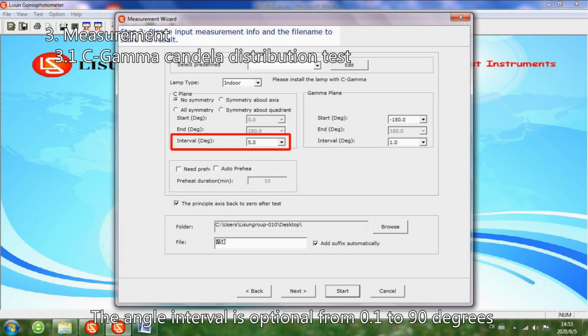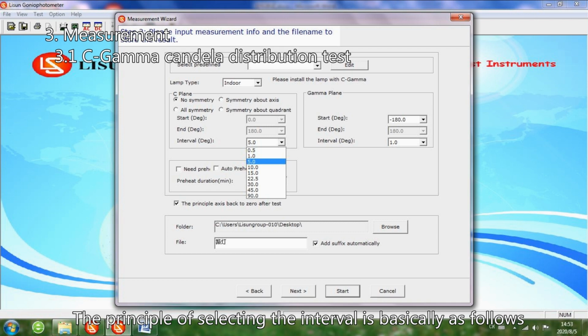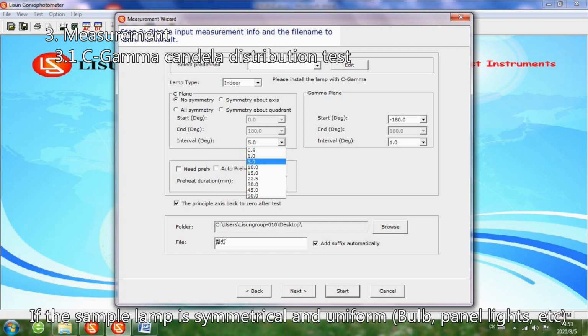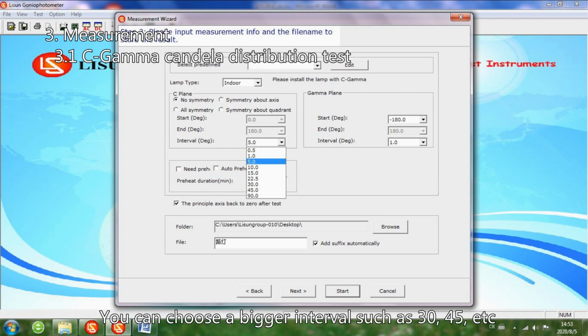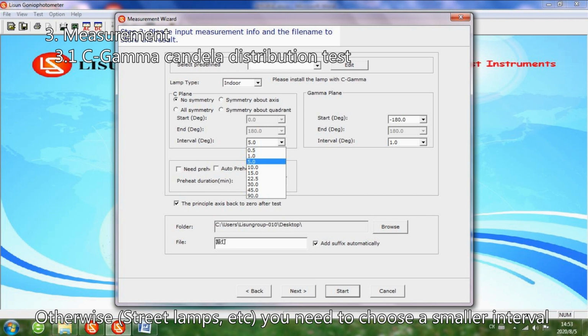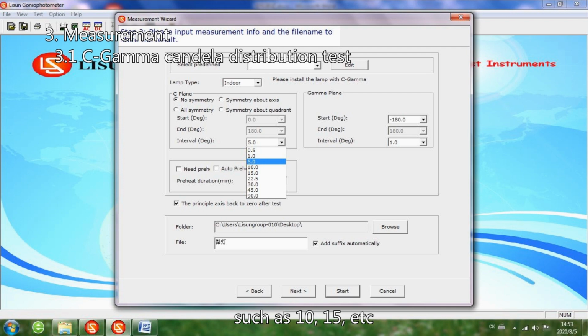The angle interval is optional from 0.1 to 90 degrees. The principle of selecting the interval is basically as follows. If the sample lamp is symmetrical and uniform, such as bulbs, panel lights, etc., you can choose a bigger interval such as 30, 45, etc. Otherwise, for street lamps, etc., you need to choose a smaller interval, such as 10, 15, etc. A bigger interval needs less time to finish the test. A smaller interval needs more time to finish the test but the data is more accurate.